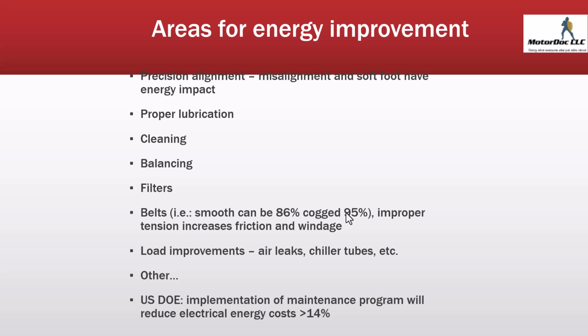Other areas to continue making improvements would be precision alignment. That's huge. I can increase my losses in the motor by up to 60% with just a standard alignment. But when I do precision alignment, I can drive that way down. Proper lubrication, cleaning, balancing, changing out filters, especially on larger machines. Belts, big deal. That's a huge deal. Load improvements such as air leaks, chiller tubes, and everything else. And basically anything on the driven equipment.